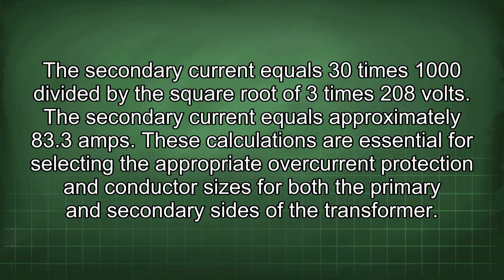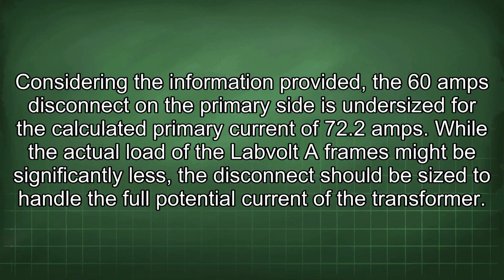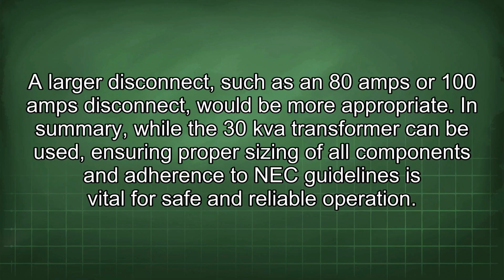These calculations are essential for selecting the appropriate overcurrent protection and conductor sizes for both the primary and secondary sides of the transformer. Considering the information provided, the 60 amps disconnect on the primary side is undersized for the calculated primary current of 72.2 amps. While the actual load of the Labvolt A frames might be significantly less, the disconnect should be sized to handle the full potential current of the transformer. A larger disconnect, such as an 80 amps or 100 amps disconnect, would be more appropriate.